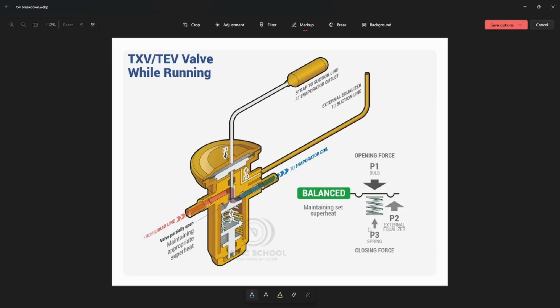And then we have our spring, which is the main closing force. That's going to be this section right here in the bottom of our valve. That's our spring. And then we have our external equalization tube, our external equalizer, which is our secondary opening force, which would bring in a secondary force of pressure. That's this line right here that feeds refrigerant in and up on the diaphragm to counteract the bulb. So we have our three forces, but it's all mechanical force. So it's all pressure balance.